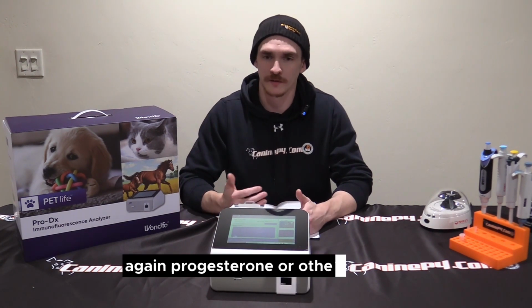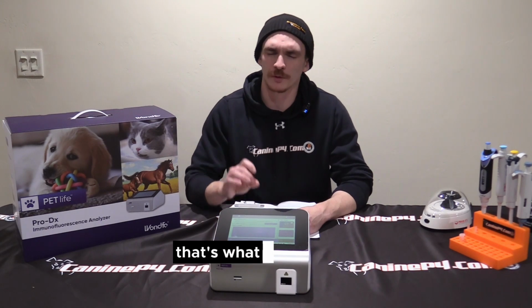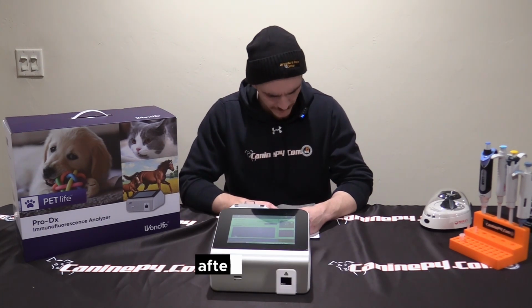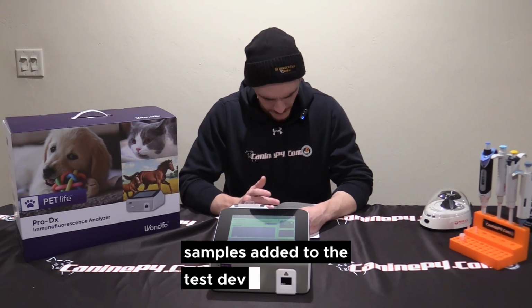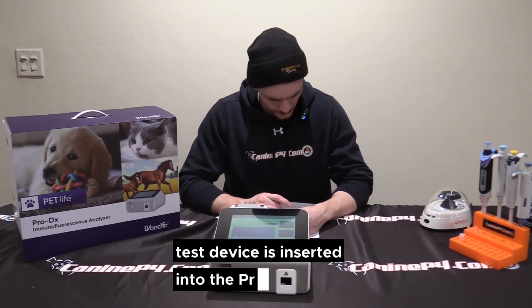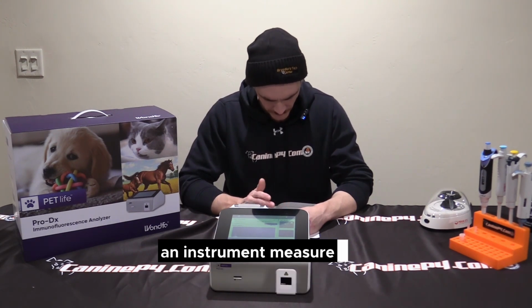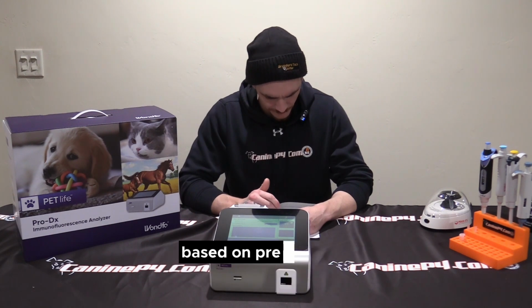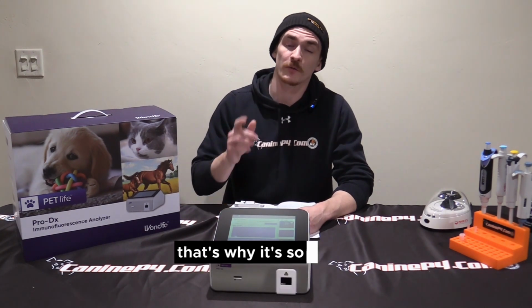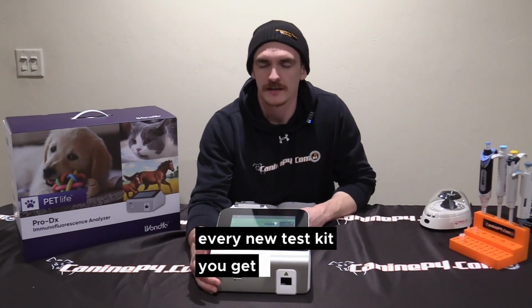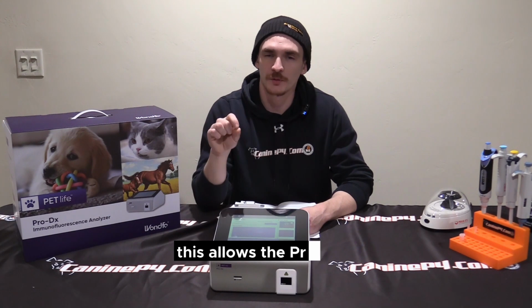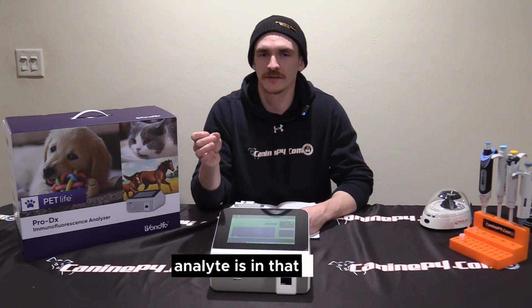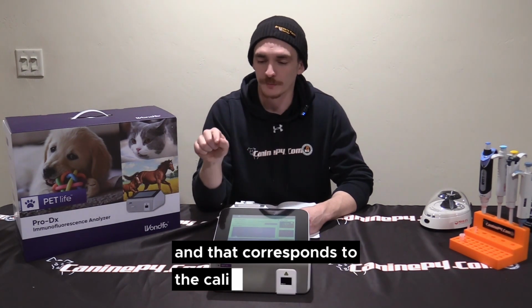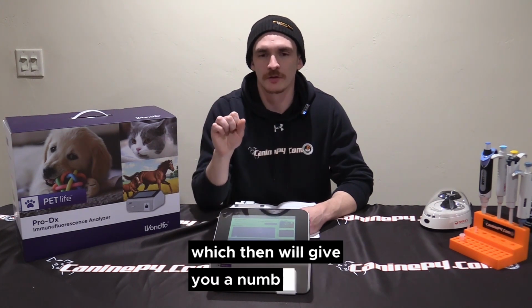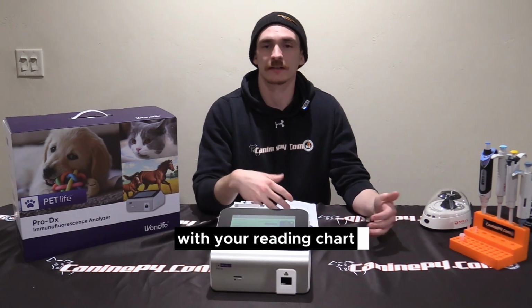Again, progesterone or other analytes. We mainly deal with progesterone, so that's what I'm focusing on here. But to continue, after a buffer mix sample is added, the test device is inserted into the Pro DX analyzer, and the instrument measures the concentration of the analyte based on pre-programmed calibration. That's why it's so important to make sure every new test kit you get to insert the ID chip and calibrate it. We'll show you how to do that in a minute. This allows the Pro DX to detect how much analyte is in that sample, and that corresponds to the calibration chip, which then will give you a number, which can correspond with your reading chart and tell you what to do with it.